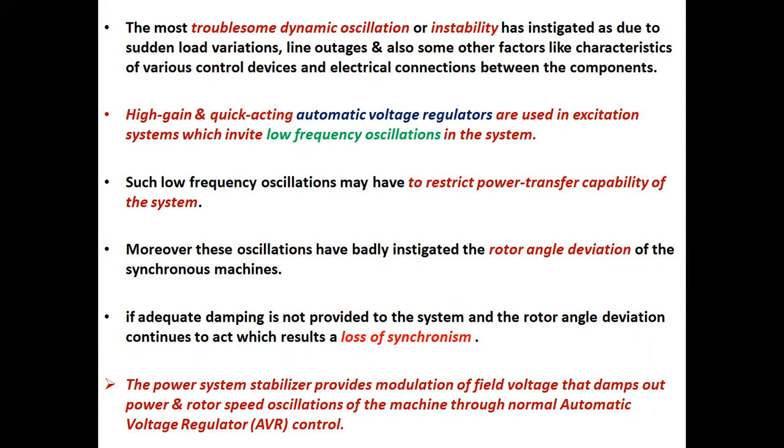Such low frequency oscillations may restrict the power transfer capability of the system. System means excitation system. Moreover, these oscillations have badly instigated the rotor angle deviation of the synchronous machines. If adequate damping is not provided to the system and the rotor angle deviation continues to act, it results in a loss of synchronism.